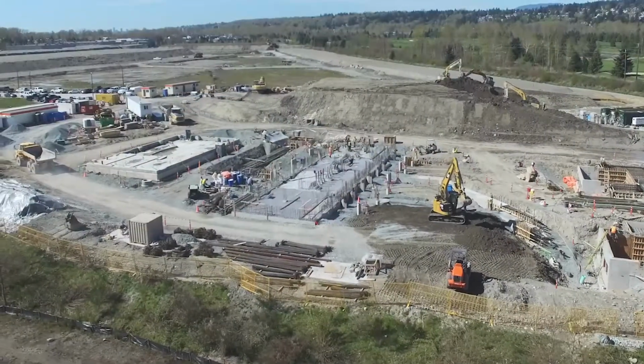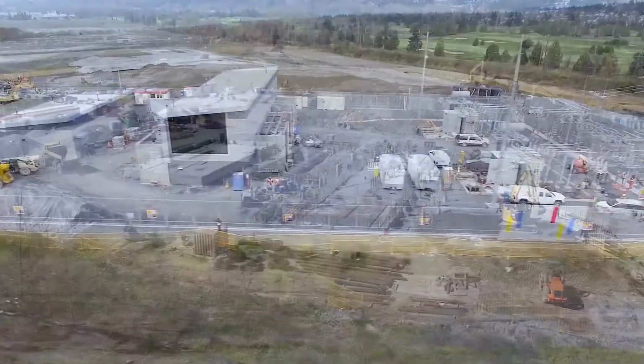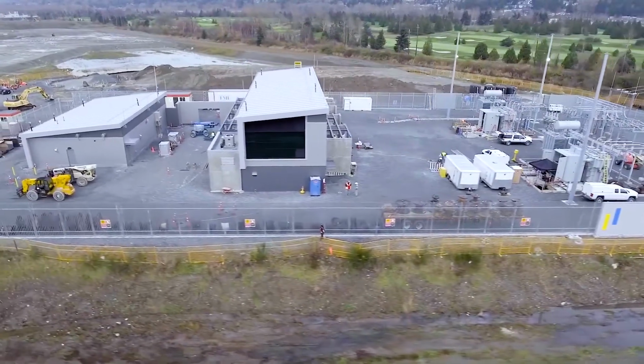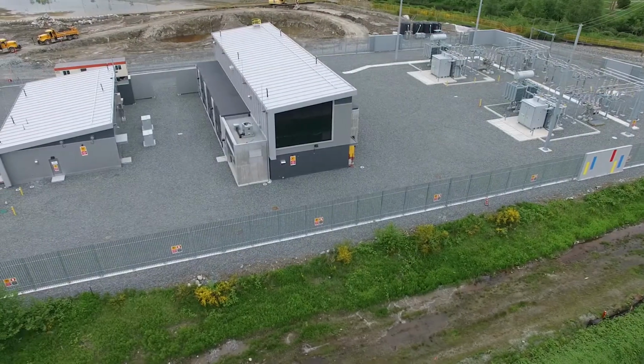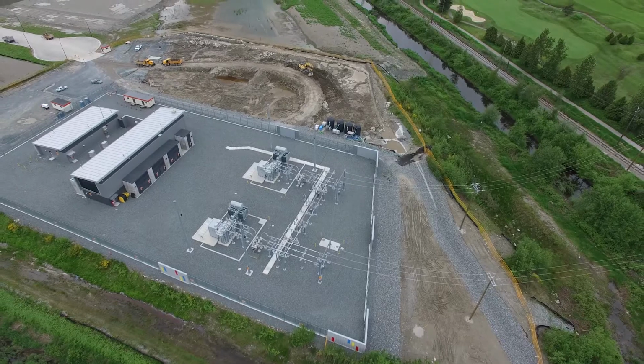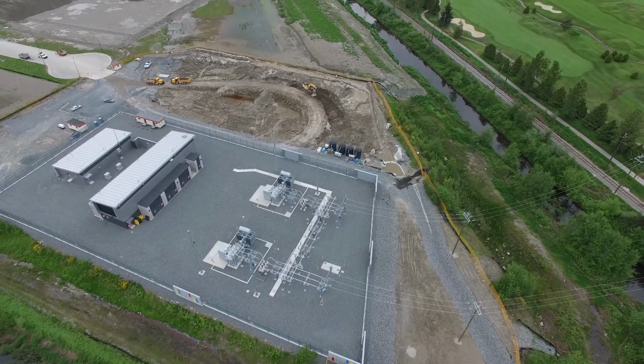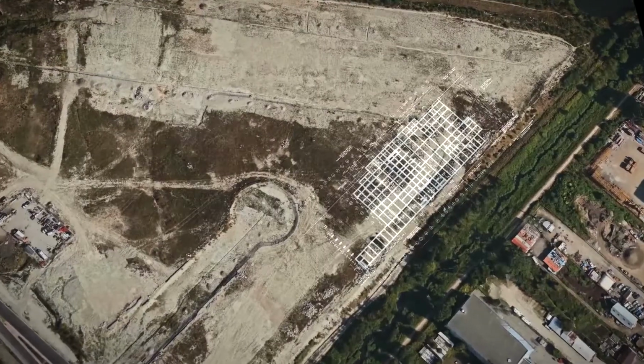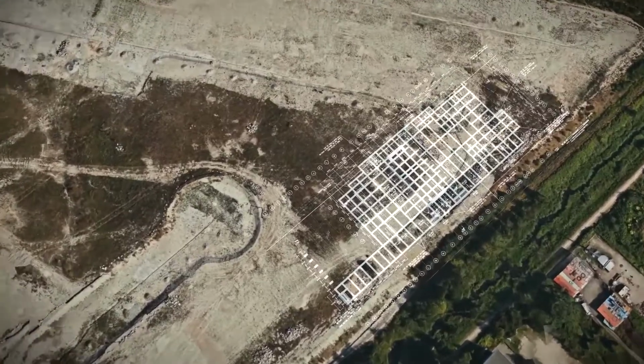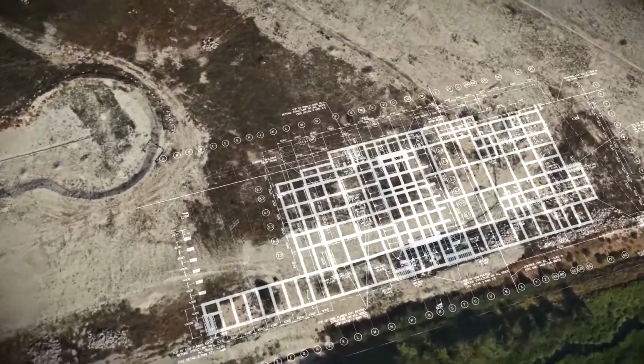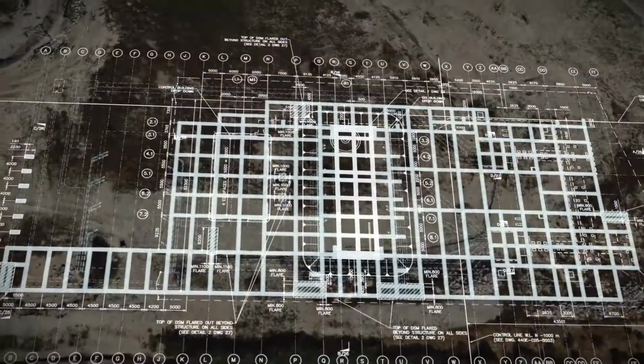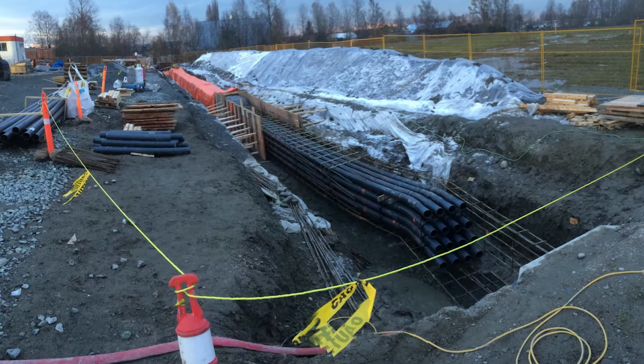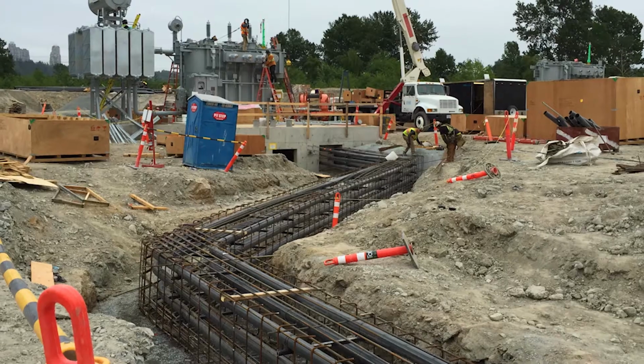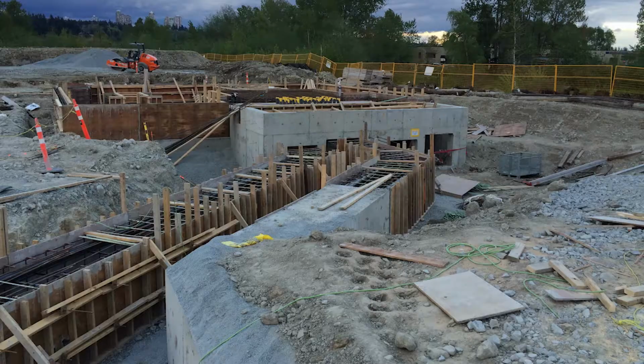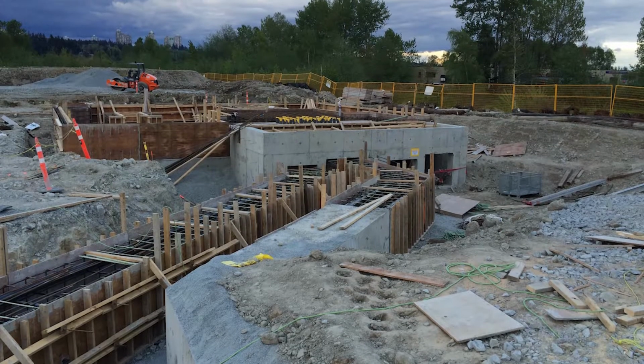As an electrical contractor, FMI has overseen the successful installation of many substations. However, this installation had unique challenges, such as building the substation on top of a grid of 20-meter deep grout-reinforced soil panels. All services and electrical duct banks needed to run along this grid of reinforcement, as the site was built on boggy material expected to compress drastically over the next 50 years.